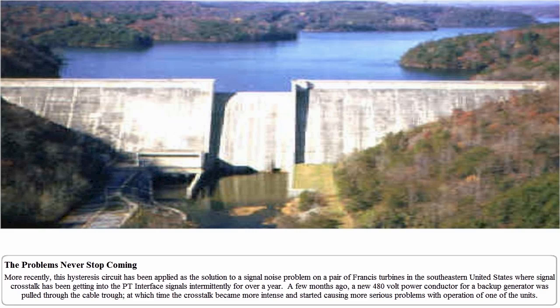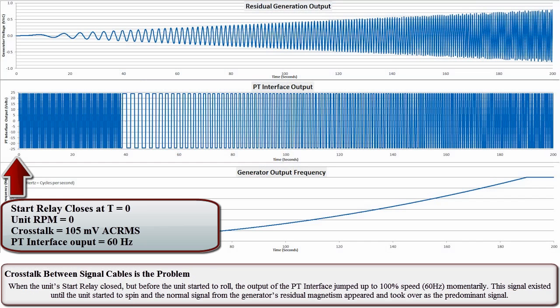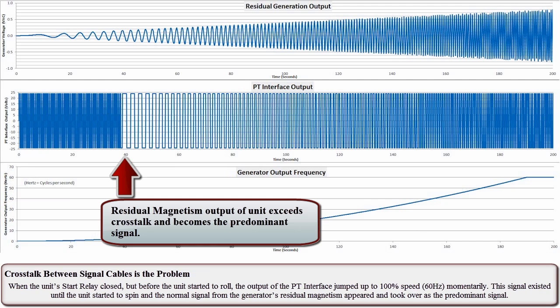A few months ago, a new 480-volt power conductor for a backup generator was pulled through the cable trough, at which time the crosstalk became more intense and started causing more serious problems with operation of one of the units. When the unit's start relay closed, but before the unit started to roll, the output of the PT interface jumped up to 100% speed, 60 Hz, momentarily. This signal existed until the unit started to spin and the normal signal from the generator's residual magnetism appeared and took over as the predominant signal.